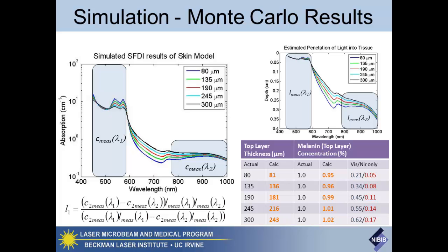Right. So the method I used, I made individual sheets, and I could physically stack them. The nice thing there is I could have a base phantom where I know the optical properties and make measurements of thin sheets that I knew the thickness of and interchange them. The one nice thing with the silicone is there's a little bit of an electrostatic surface, so you could place the sheet on there and push out air bubbles and have tight optical contact without having any intermediary substance in between.